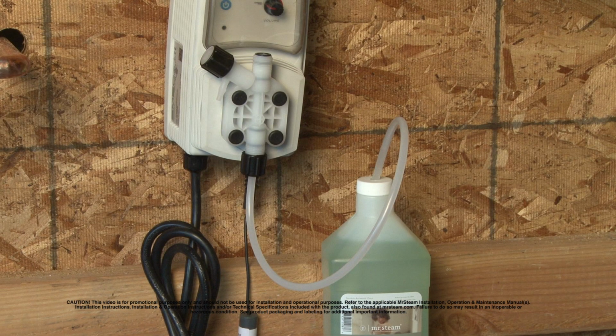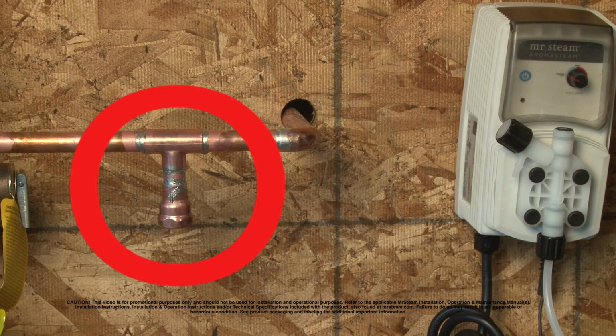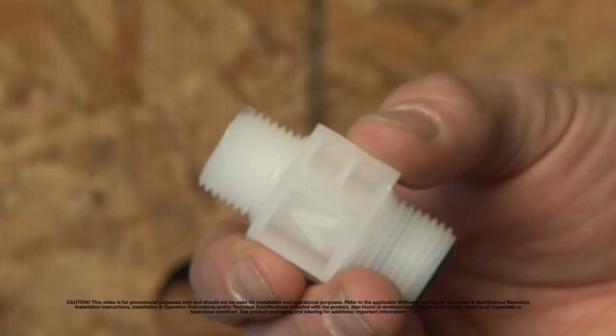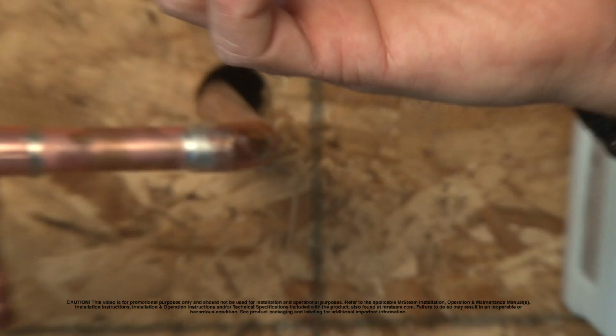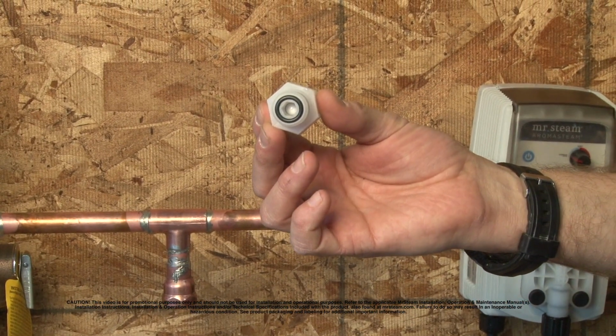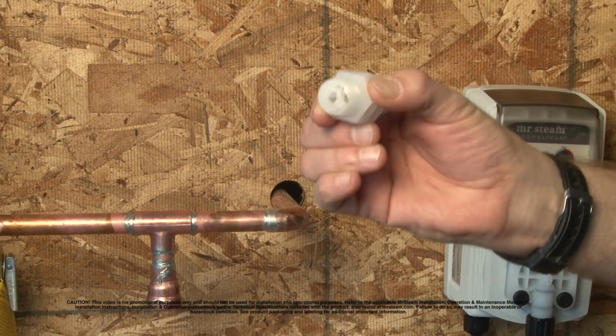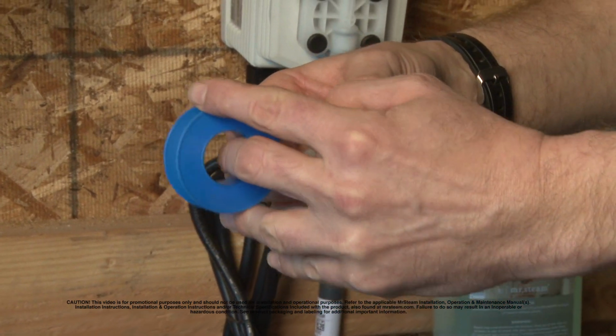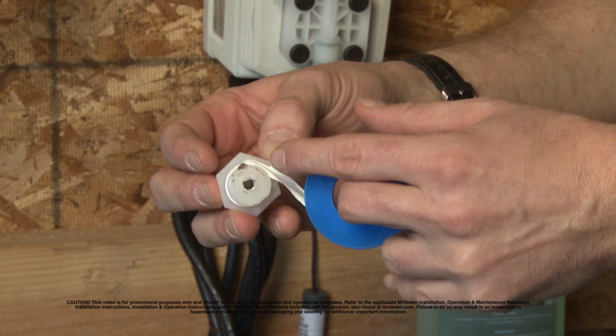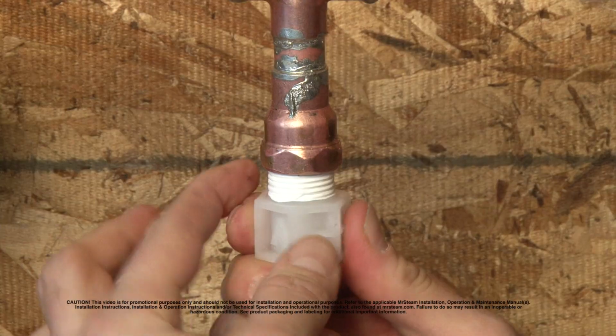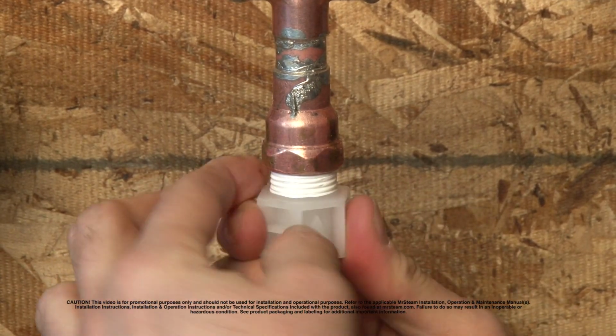In order to get the oil from the pump to the steam line, we need a 1/2 inch NPT T-fitting on the steam line within 10 feet of the steam head. This is an atomizing nozzle. You'll notice that one end of the atomizing nozzle has a black ring on it. That connects to your hose. Wrap Teflon tape around the threads on the other end of the nozzle and screw that into the 1/2 inch NPT T-fitting on your steam line.